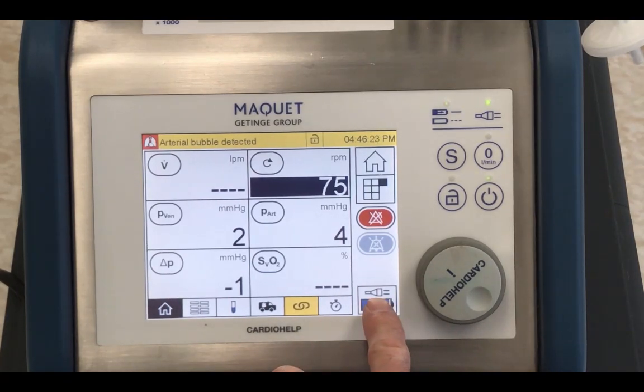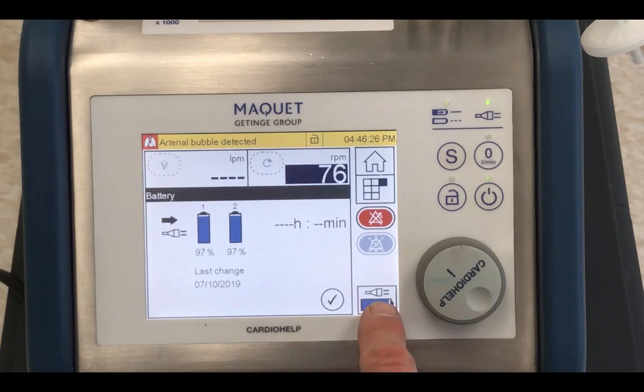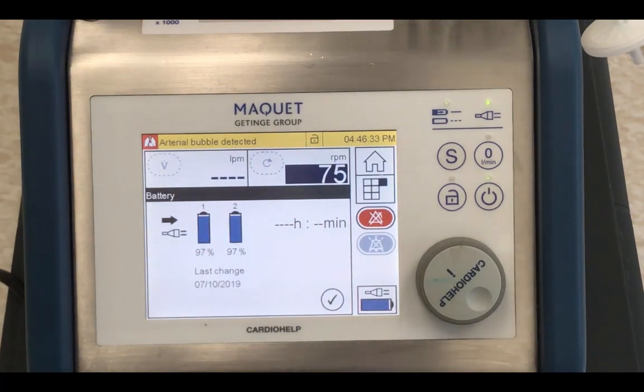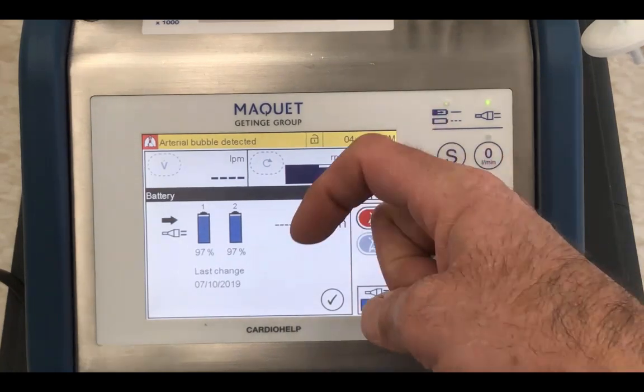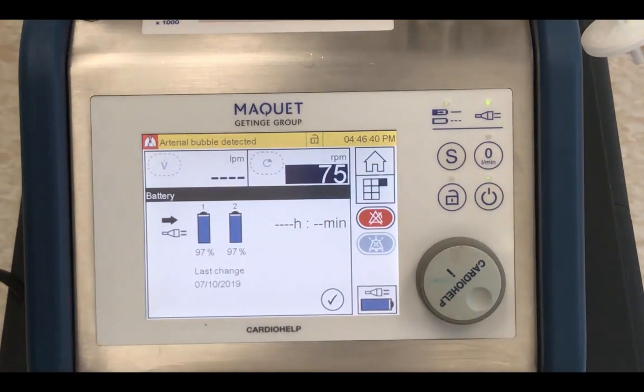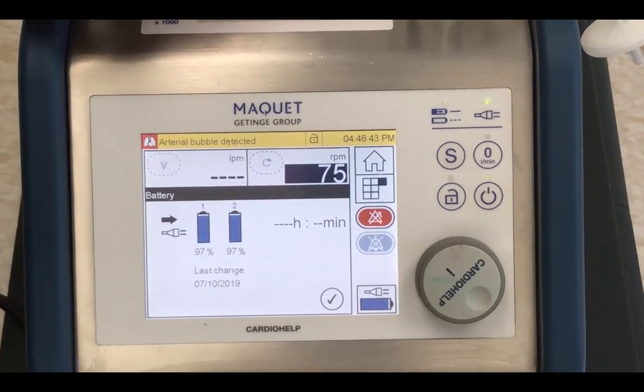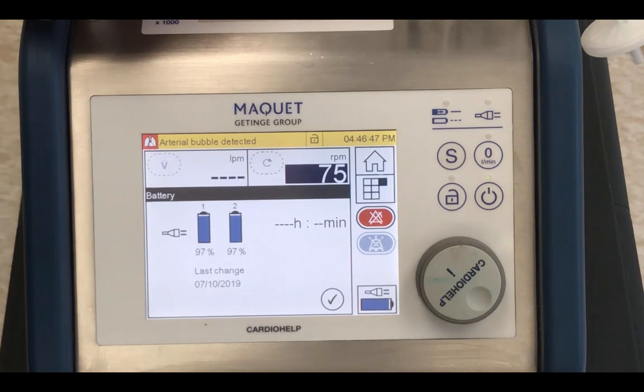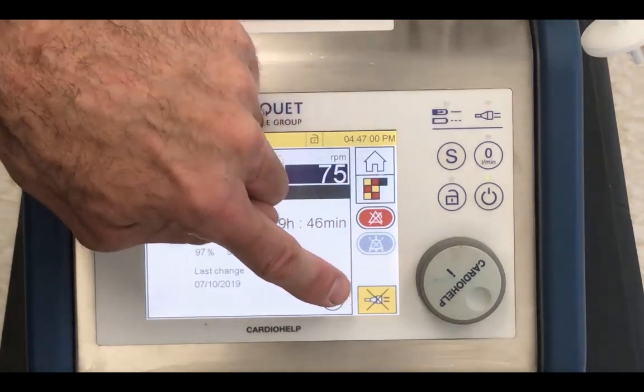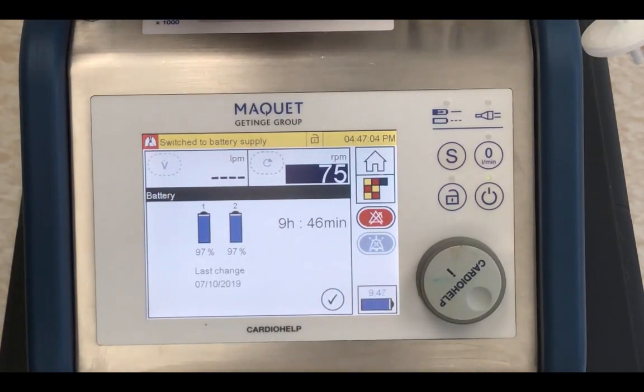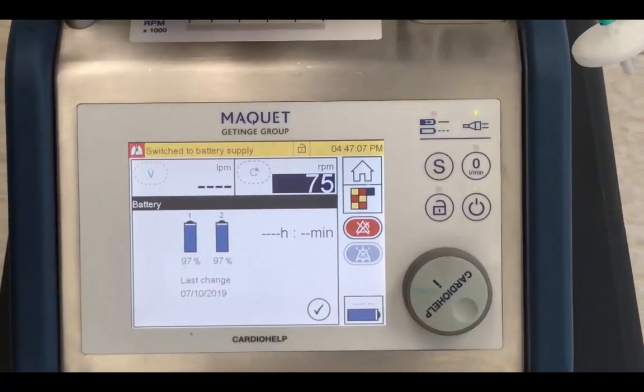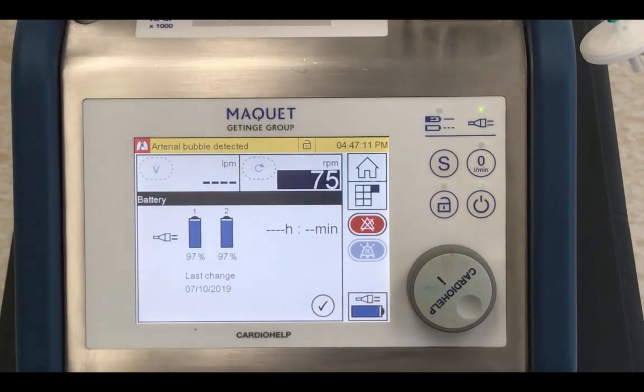It tells you that we are not using battery. We're using power because you see the plugged in symbol here. And if you click on that, it tells you that we have a bank of batteries and they're 97% charged. I'm going to reach down here and unplug that system for a moment, and we can watch what happens to that. You can see when you unplug that the icon starts to flash. We're in global override, so it's not giving any audible alarms, but it is flashing that we are not plugged into the wall anymore, and I'll go ahead and plug that back in. And it immediately corrects itself.